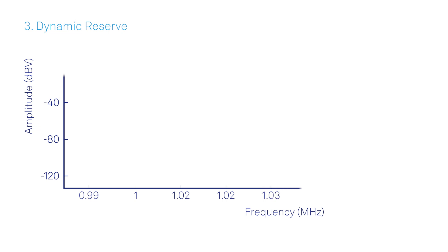Another key parameter to consider is the lock-in amplifier's dynamic reserve, which quantifies the instrument's capability to withstand disturbing signals and noise while maintaining a certain measurement accuracy, usually 1%. For example, with a 120 dB dynamic reserve, you can measure a signal of 1 µV with 1% accuracy in the presence of 1V disturbance.